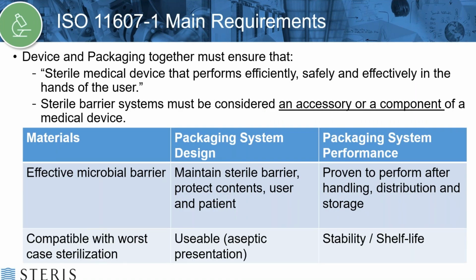So the main requirements of ISO 11607-1: the device and packaging together must ensure that the sterile medical device performs efficiently, safely, and effectively in the hands of users. And the sterile barrier systems must be considered an accessory or a component of the medical device. So the materials need to act as an effective microbial barrier. It's going to, again, protect the sterility of your product from being compromised.